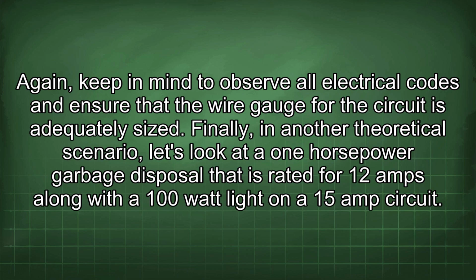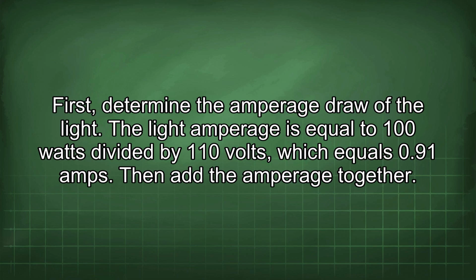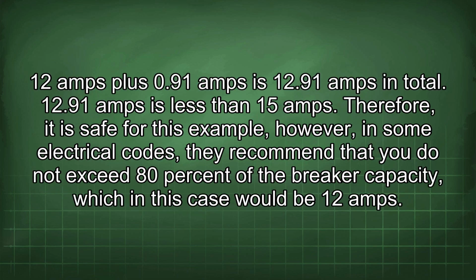Finally, in another theoretical scenario, let's look at a 1 horsepower garbage disposal that is rated for 12 amps along with a 100 watt light on a 15 amp circuit. First, determine the amperage draw of the light. The light amperage is equal to 100 watts divided by 110 volts, which equals 0.91 amps. Then add the amperage together. 12 amps plus 0.91 amps is 12.91 amps in total. 12.91 amps is less than 15 amps. Therefore, it is safe for this example.